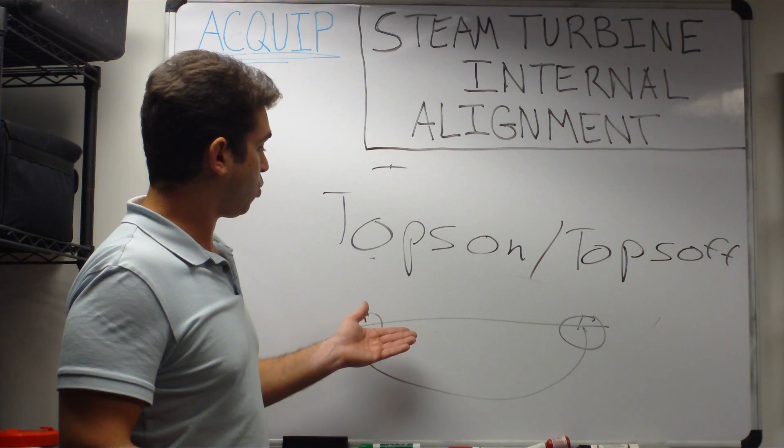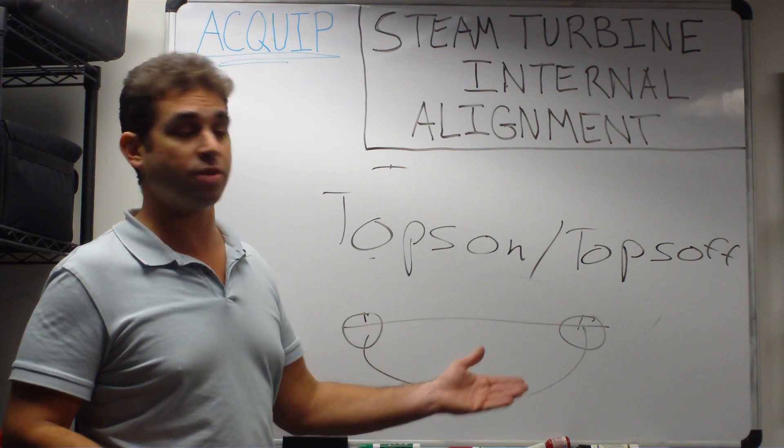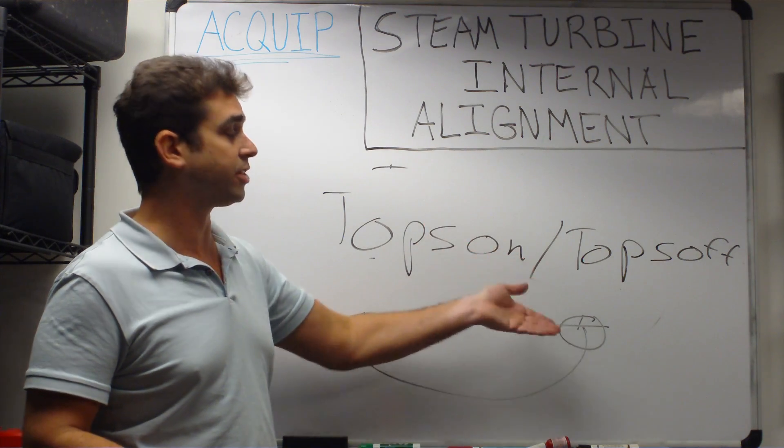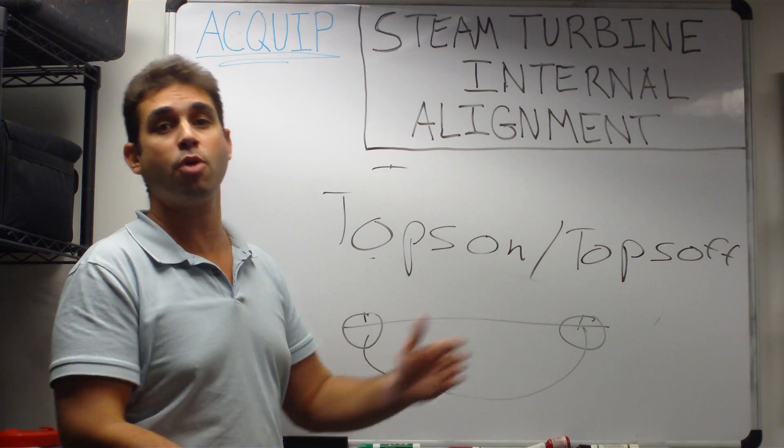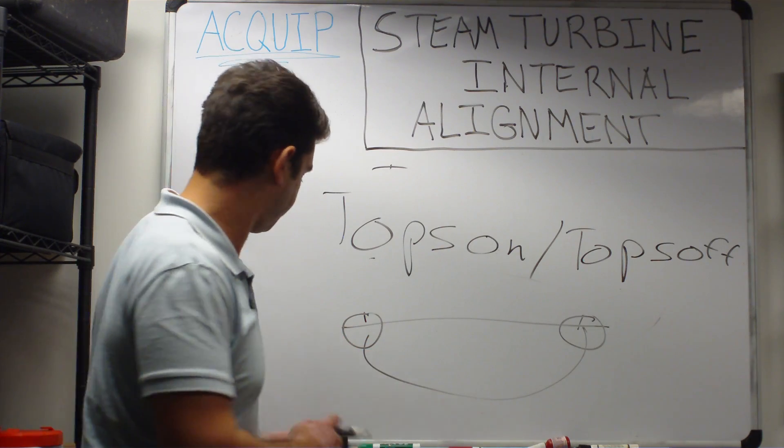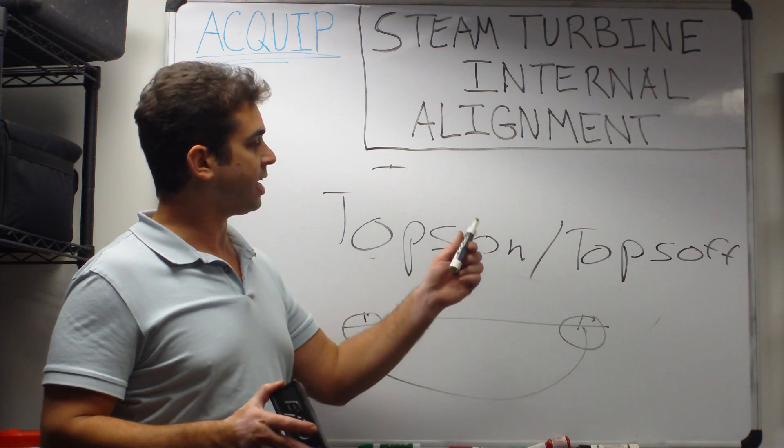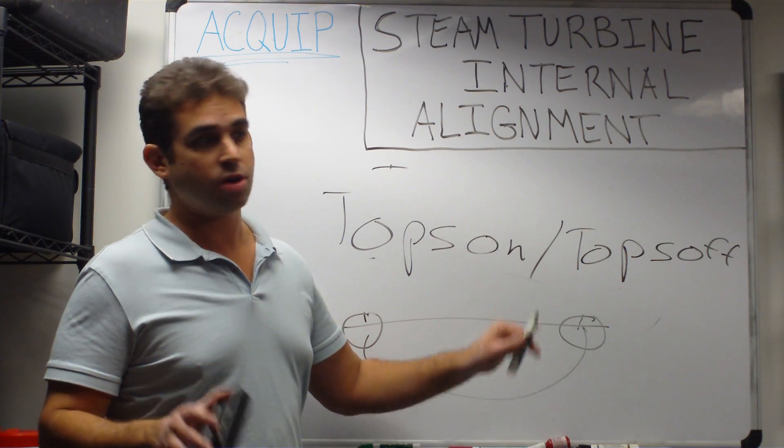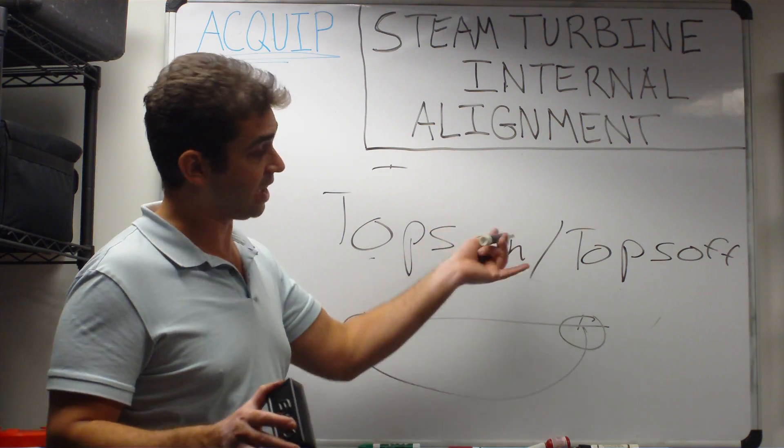While we're doing that, we're able to make all of our adjustments more easily since the top is off, and we can always calculate for the top being back on with that initial top on to top off deviation. This type of alignment is the best kind to do for a steam turbine, and it's the only kind that you can do for a gas turbine.